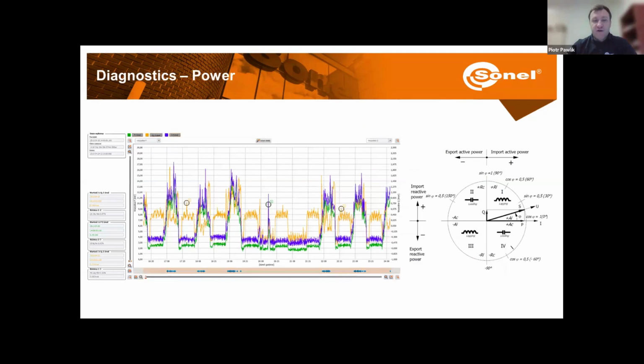Also, when we connect bigger loads, we need to look at the powers, and there's active power and reactive power that we are concerned about. So for the reactive power, the chargers, as converters, generate capacitive reactive power in most of the cases. Since excess reactive power is not desirable, exceeding the contractual value with the power utility may result in some financial charges and fines. So it is worth controlling the level of the reactive power.